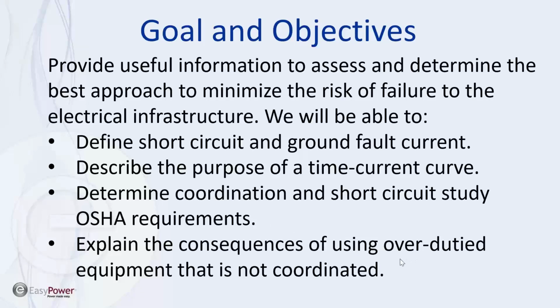And we'll talk about the consequences of over-duty equipment. When I say over-duty equipment, I'm talking about equipment that is not rated for the fault current that is available. So we'll talk about what that all means, and if the equipment's not coordinated, that's going to be a factor as well. So we'll talk about what this coordination and short circuit stuff is all about.